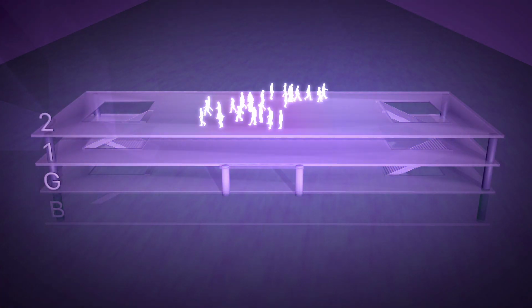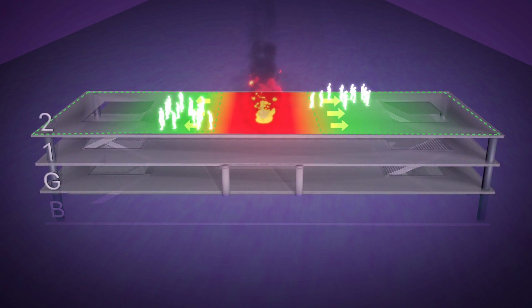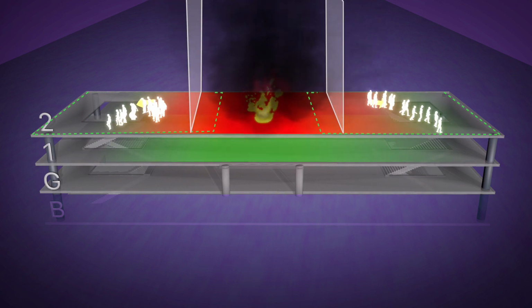Progressive horizontal evacuation is a process that allows people to move from a zone within the building in which the alarm is sounding, known as an evacuation zone, to an adjacent evacuation zone in which the alarm is not sounding, known as a place of relative safety. The adjacent safe zone may be on the same floor level and in clear line of sight to the evacuation zone, but because of the design of the building and the supportive life safety features such as smoke extraction, the area will be protected from the immediate effect of the fire.